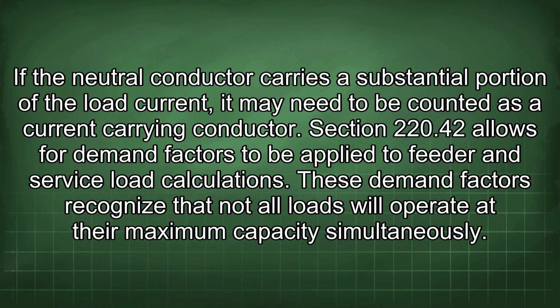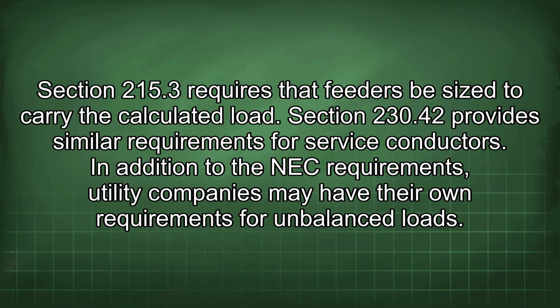Section 220.42 allows for demand factors to be applied to feeder and service load calculations. These demand factors recognize that not all loads will operate at their maximum capacity simultaneously. Section 215.3 requires that feeders be sized to carry a calculated load. Section 230.42 provides similar requirements for service conductors.